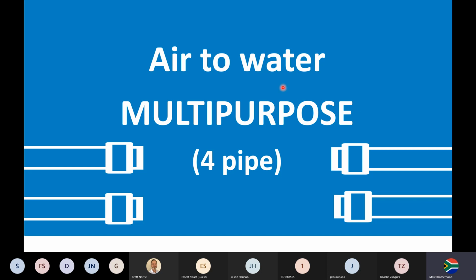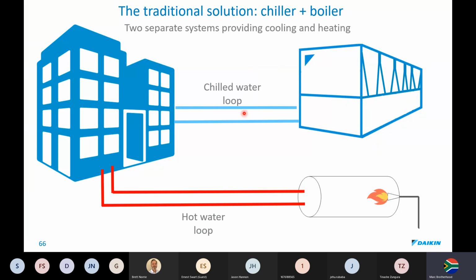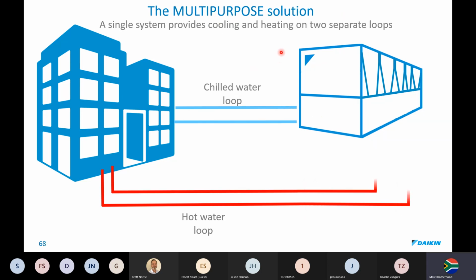Another unique product that we offer is the 4-pipe chiller, air to water. It's a multi-purpose chiller. So if you wanted to provide heating for geysers or boilers for a hospital, hot water for the kitchen, your laundries, you would typically have a boiler running, supplying hot water, and your chiller providing cooling. So Daikin have the solution now where this chiller can make hot water as well as cold water, as well as doing it at both the same time. Most chillers can either work as a heat pump, or work as cooling only. This chiller can do cooling and heating at the same time.